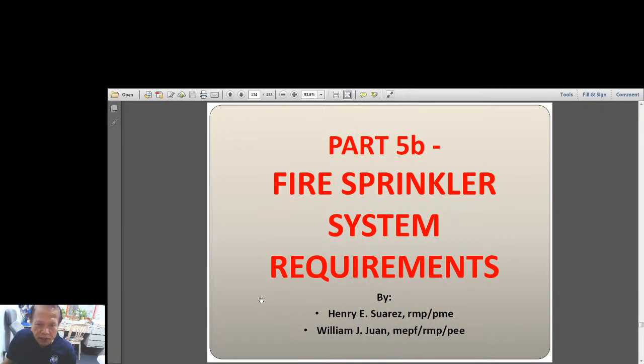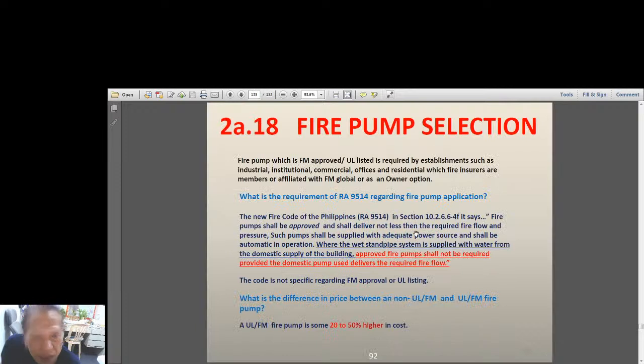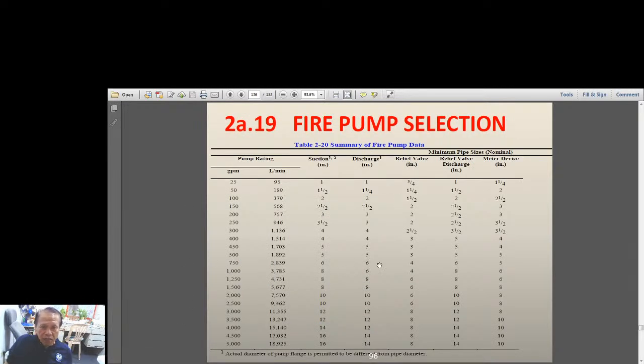Then the fire sprinkler system requirements. Again, as long as the fire pump has enough capacity, then no need for that. For UL/FM requirements, usually the UL/FM required pumps are almost 50% higher. That means 150%. Here is just the table of the fire pumps. You will notice the GPM capacity here and the corresponding intake pipe and discharge pipe. Okay, so the first column is GPM, the second column is the volume flow in liters per minute.